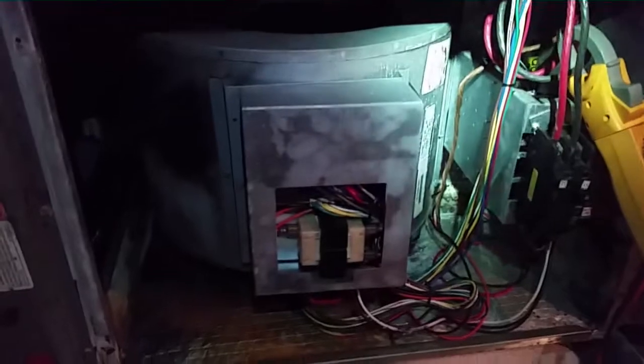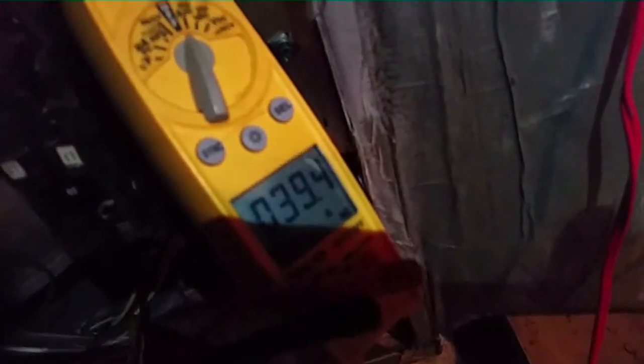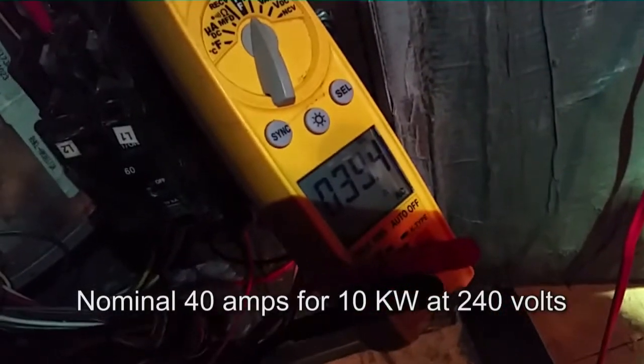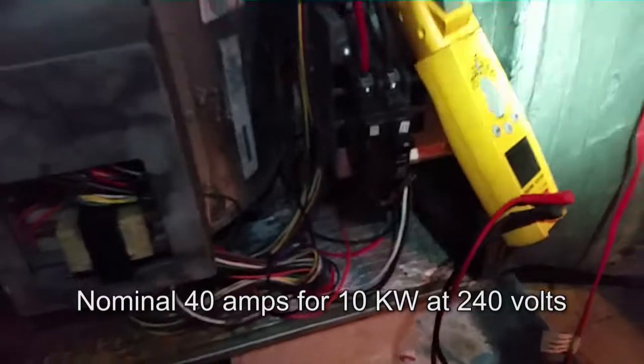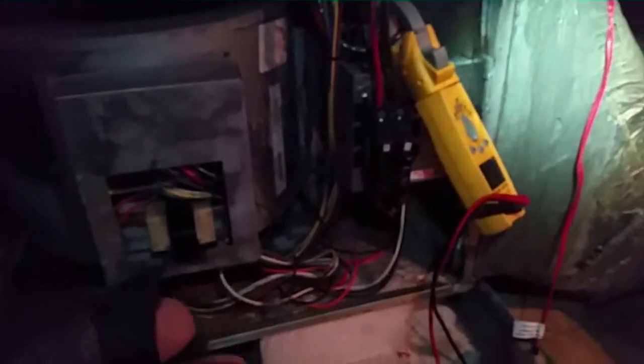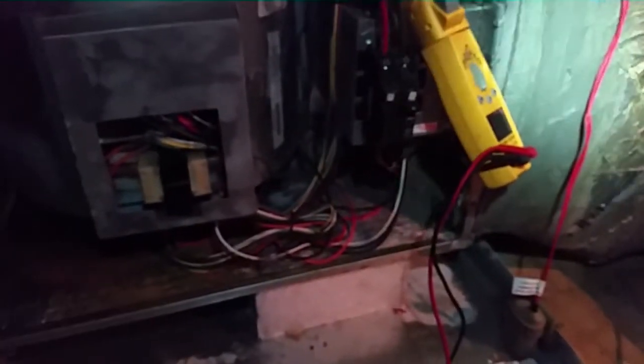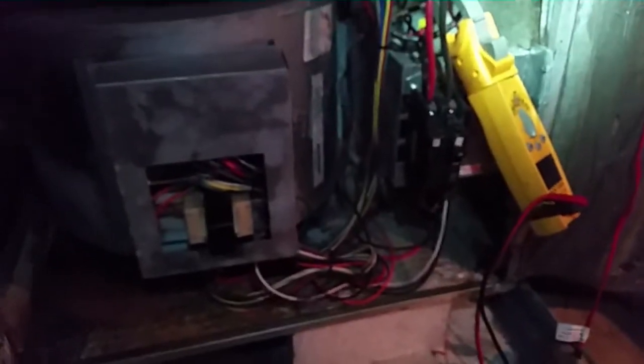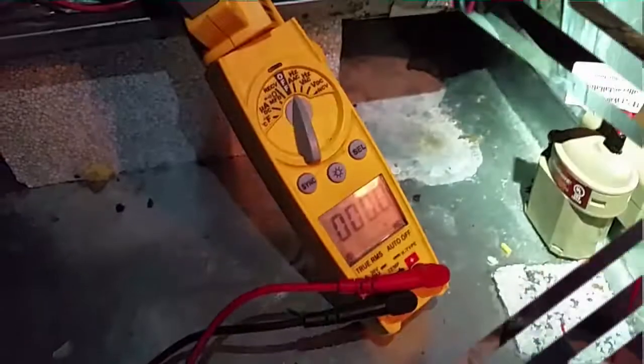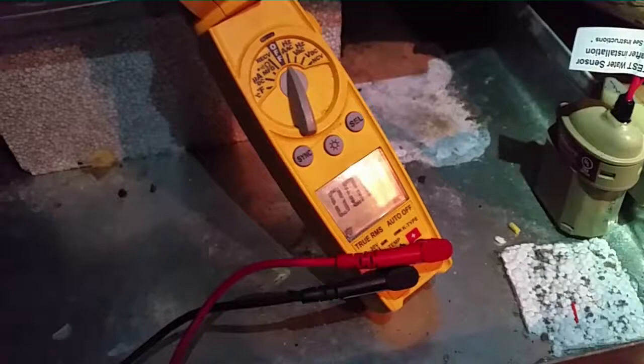Guys, we're up at the Rheem air handler. It is an ECM motor, 15 SEER. The heat strips are on like they are supposed to be, which is good. We're going to take that heat strip amperage and the voltage, subtract out the blower amperage, and see if we can get a rough CFM from our electric heat. Our ECM blower is running at 0.8 amps. With the door on, it'll actually go up.